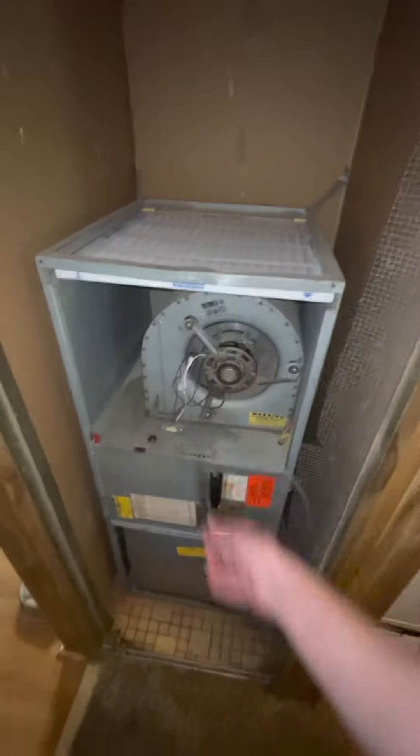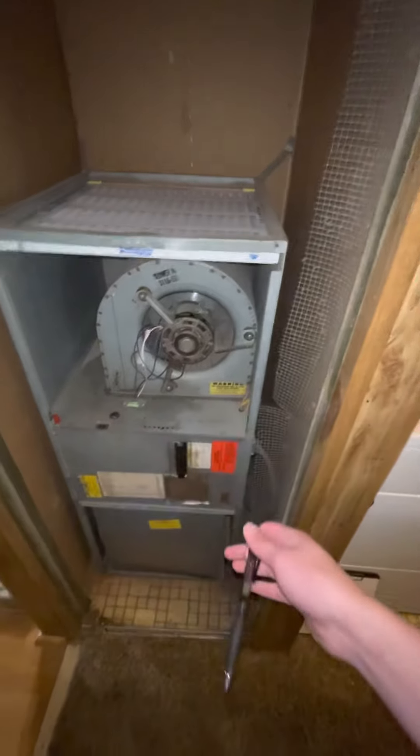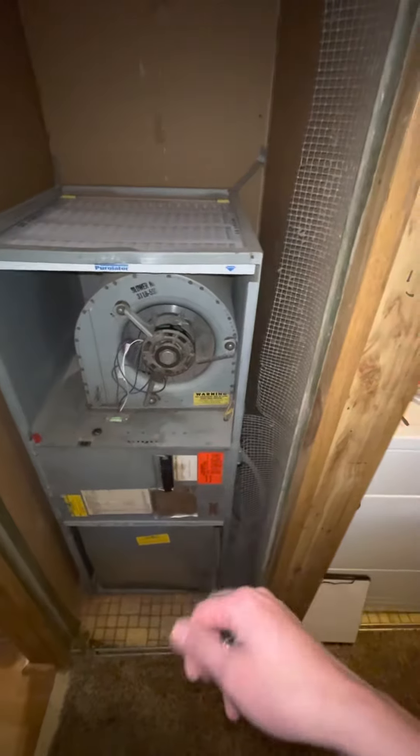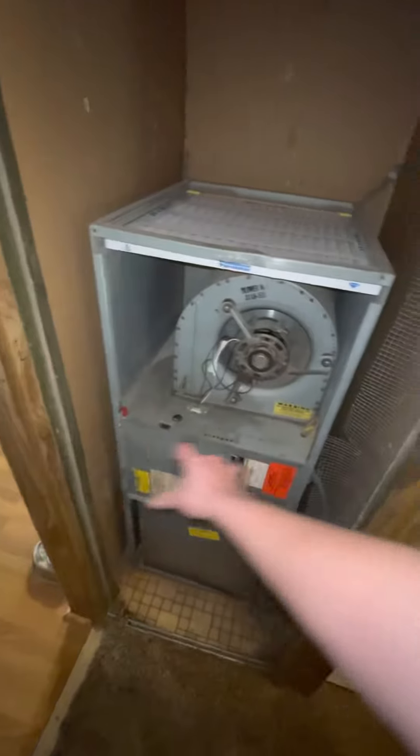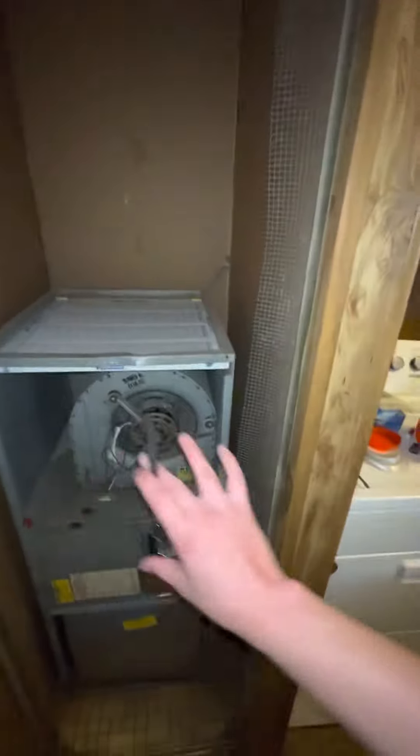This one has strictly a downflow, due to the manufactured home design for the house. It's done a very good job overall, so we're just going to be sticking with the overall size. We are 20 wide by about 52 inches, top to bottom on this guy. It doesn't have the door on it now, but that is the door that goes on it — it's completely open up here, which is perfect for airflow coming up through.